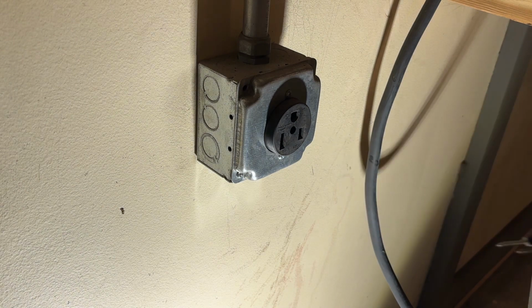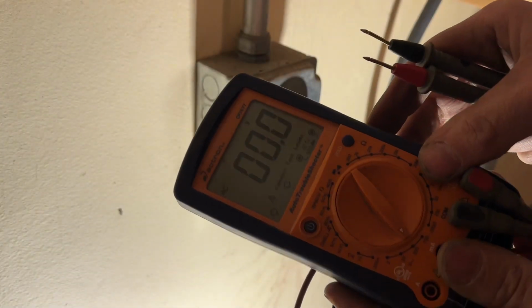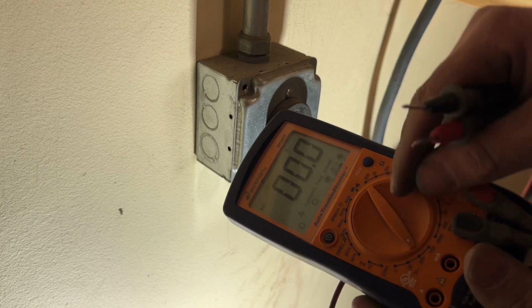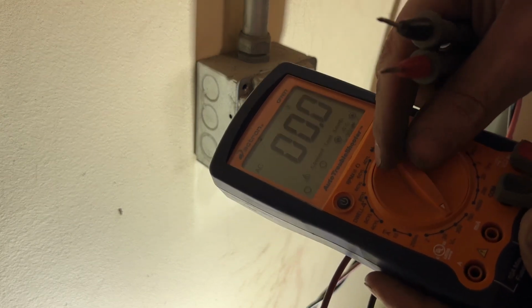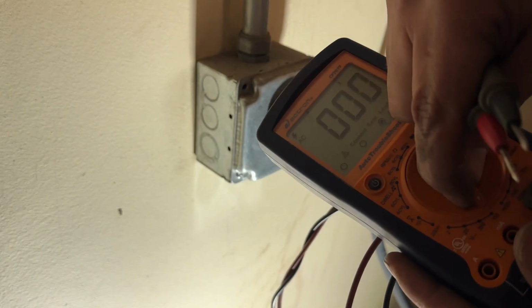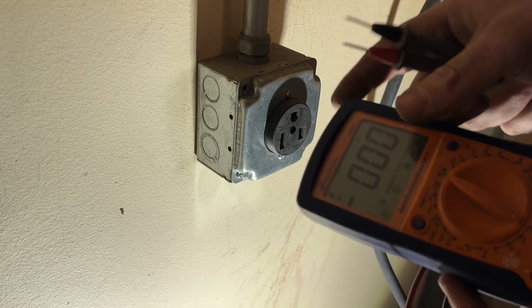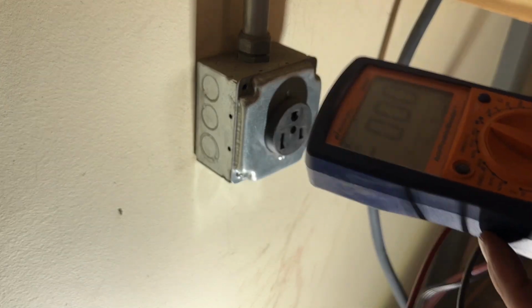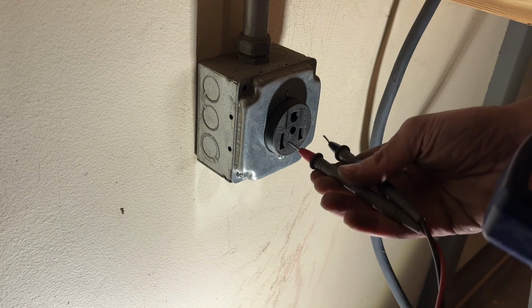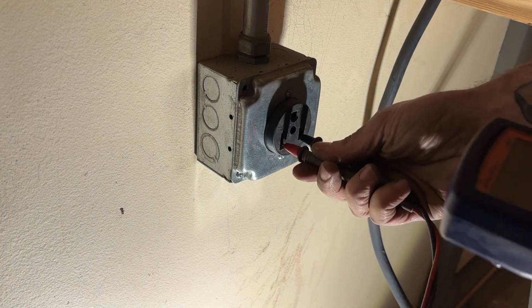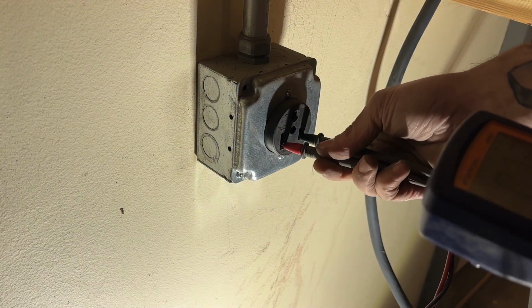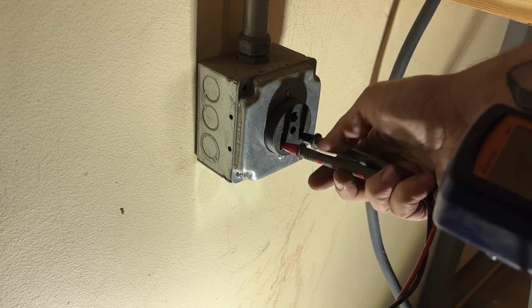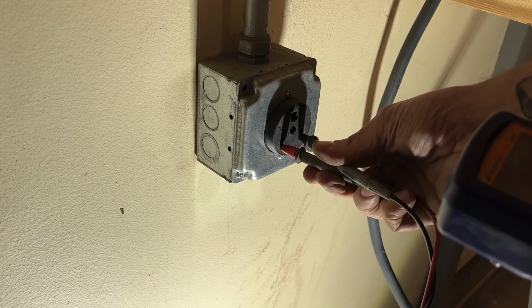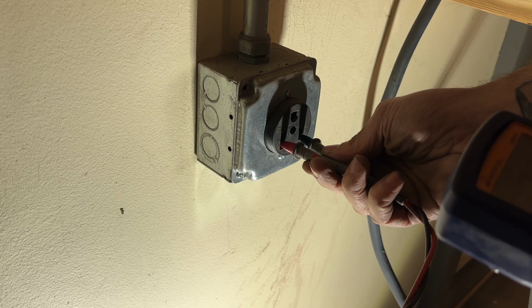So what we're going to do is take the meter—you should be able to see this—we were on the 200 volt scale, but the problem is this is going to be over 200 volts. So I put it on the 750 volt scale, and we're going to carefully insert those in there and see if we can't get a reading. There we go.